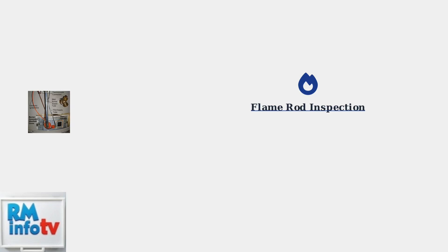Start by checking the flame rod wire connection to ensure it's secure and properly attached. Carbon buildup on the flame rod is a common issue. Clean the flame rod thoroughly to remove any carbon deposits that could interfere with flame detection.